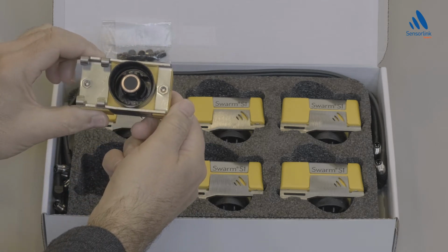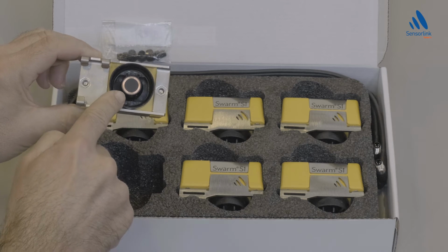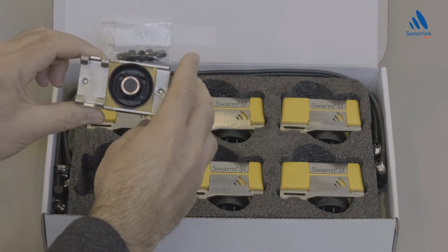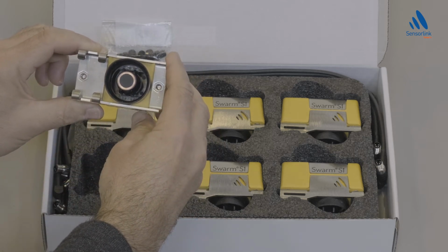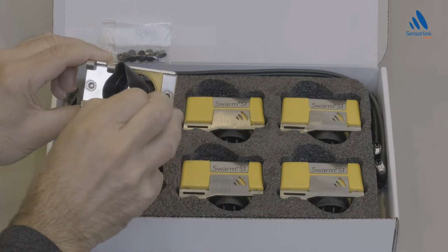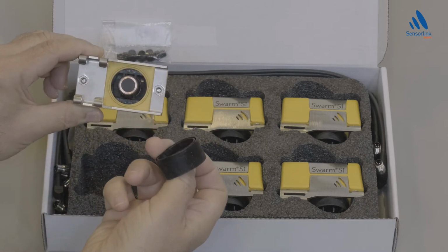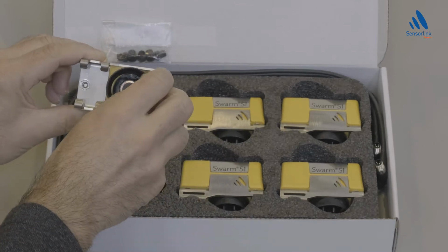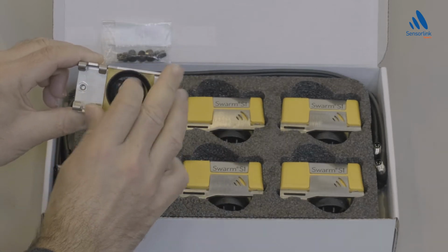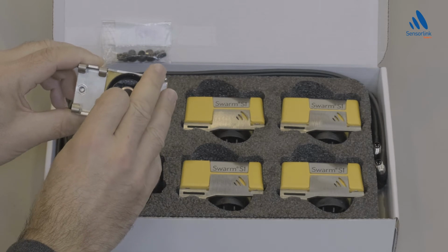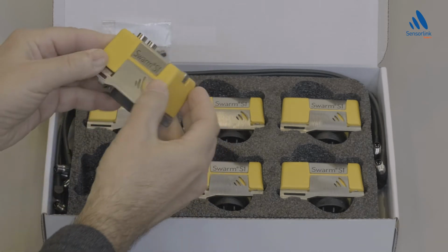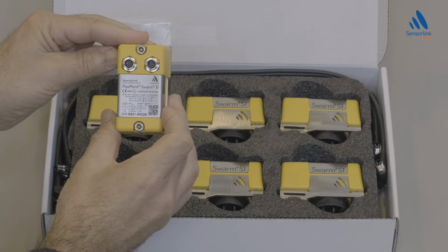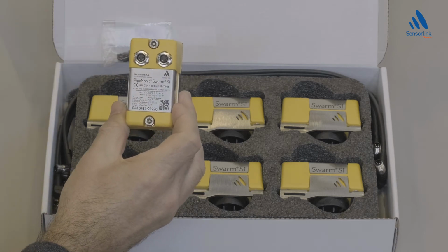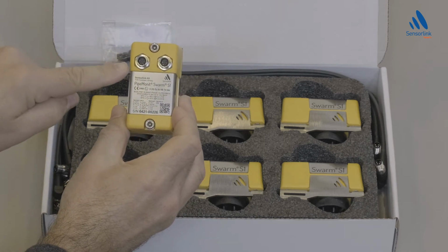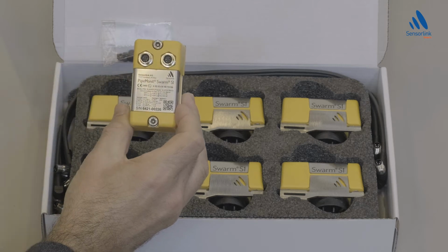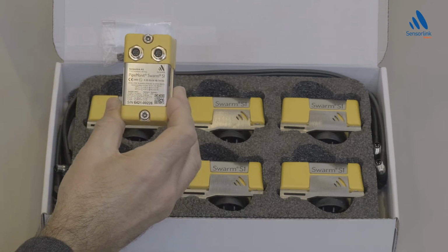This is the ultrasound transducer that is being pressed directly onto the pipe. There is also an integrated temperature sensor inside the ultrasound transducer. A rubber seal is used to avoid dirt, water and other debris from entering the area and degrading the contact between the pipe and the sensor. The Swarm SI has two connectors providing power and RS485 communication between the data logger and Swarm SI sensor. There is no difference between these contacts, so either one of them can be used when connecting to the sensor.